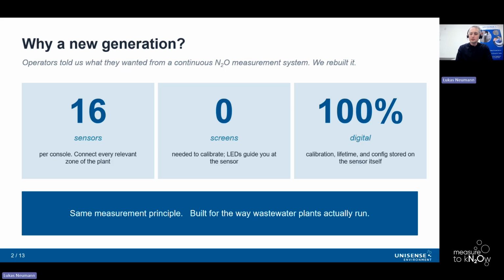Why was there a new generation in the first place? So we didn't just build this because the previous one needed updating, but we rebuilt it because operators told us what they really needed in their daily use, and we wanted to integrate these things. And here, 3 numbers really tell the story. With the new system, you can have 16 sensors per console. So one console can now effectively cover every relevant zone of a treatment plant, whether it's the aerobic, anoxic, side stream, reject water, all in one screen.